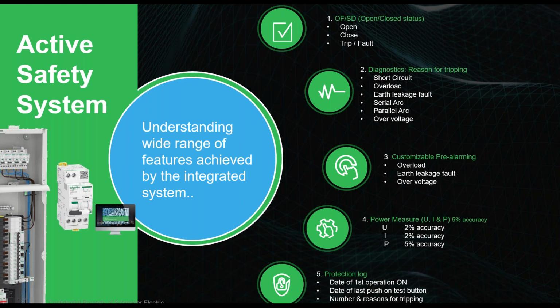We've also got the ability to have customizable pre-alarming, so it can tell us if there is a near overload or some earth leakage fault or some over voltage, but we can have that in a pre-alarm before the problems occurred. We get the ability to have power measurement, so whether it's voltage, current, power. We get protection logs, so the date of the first operation of that device, the date of the last push on the test button, and the number and reasons of tripping. These are all attributes or levels of information that come when we integrate this layer of connectivity and digitization to a single device.